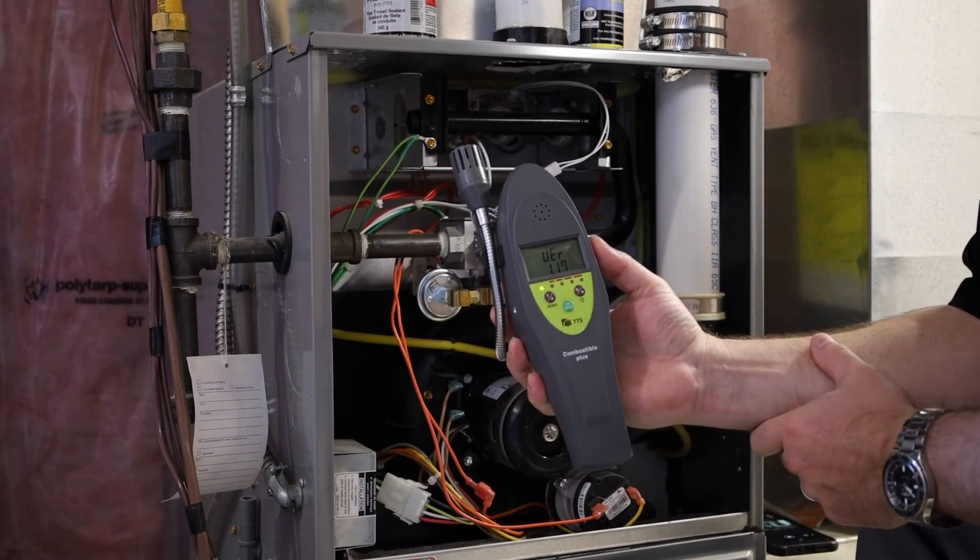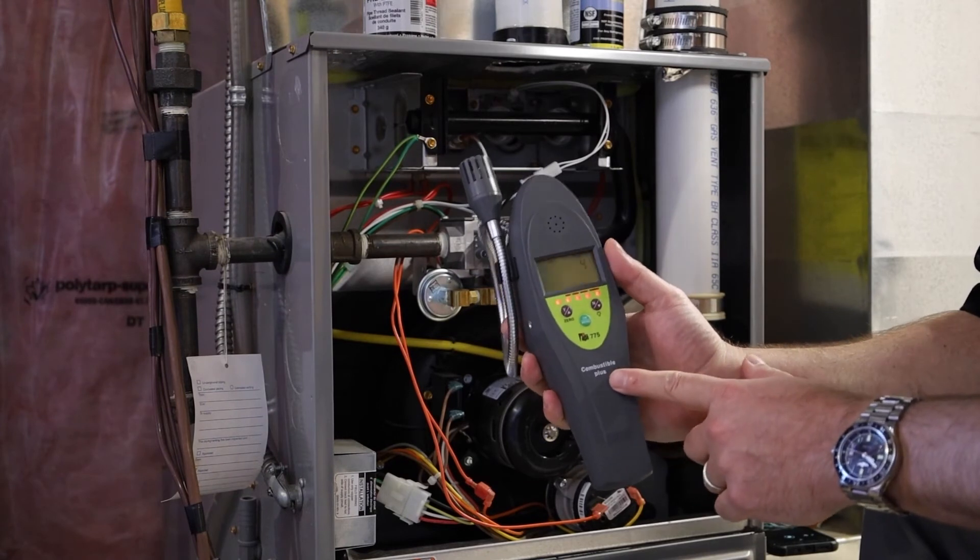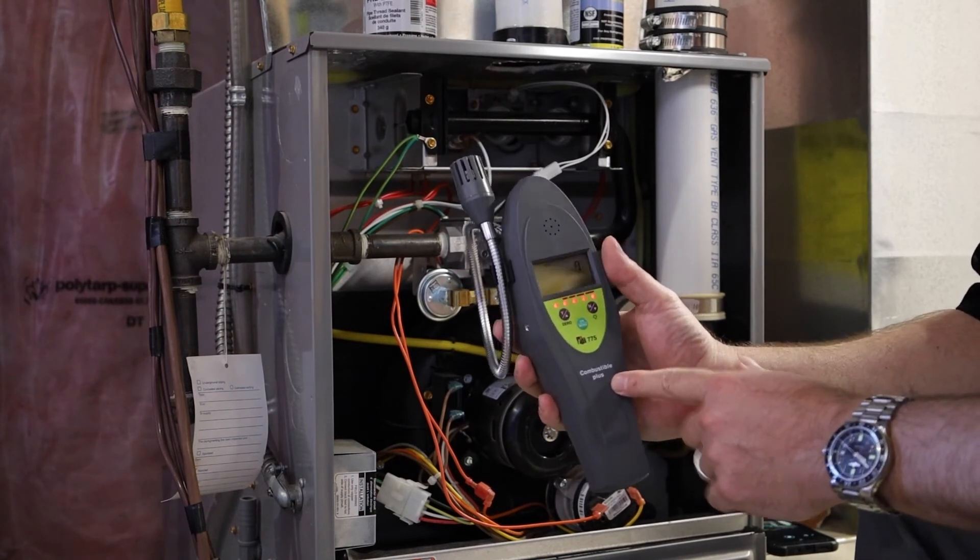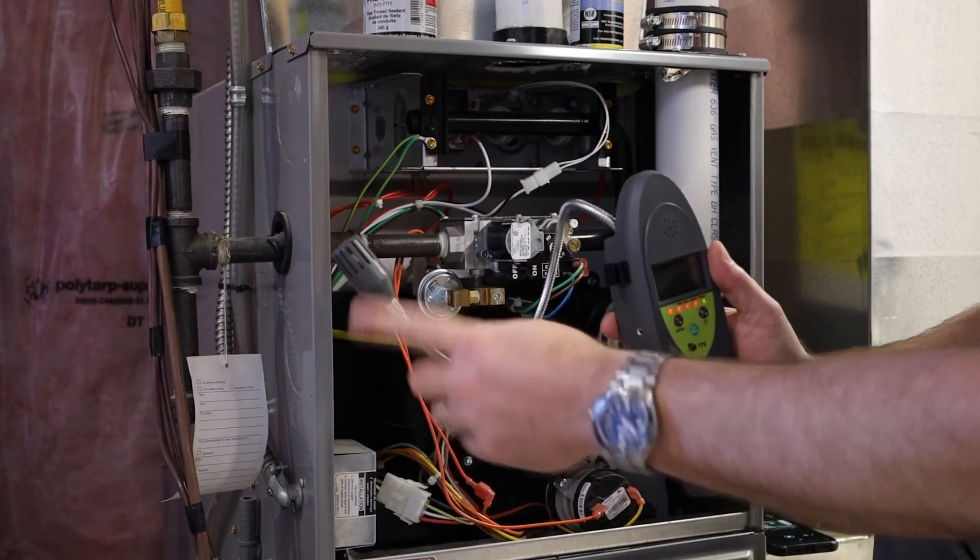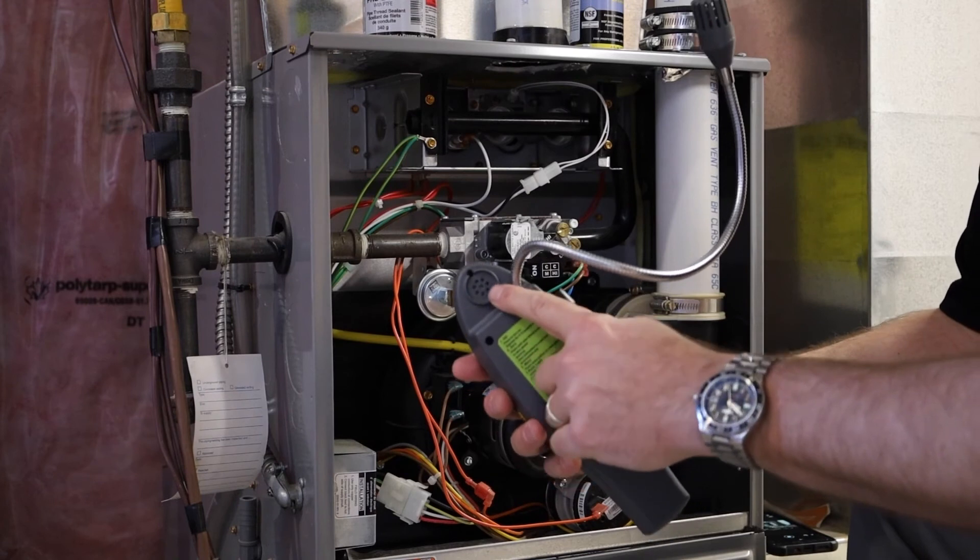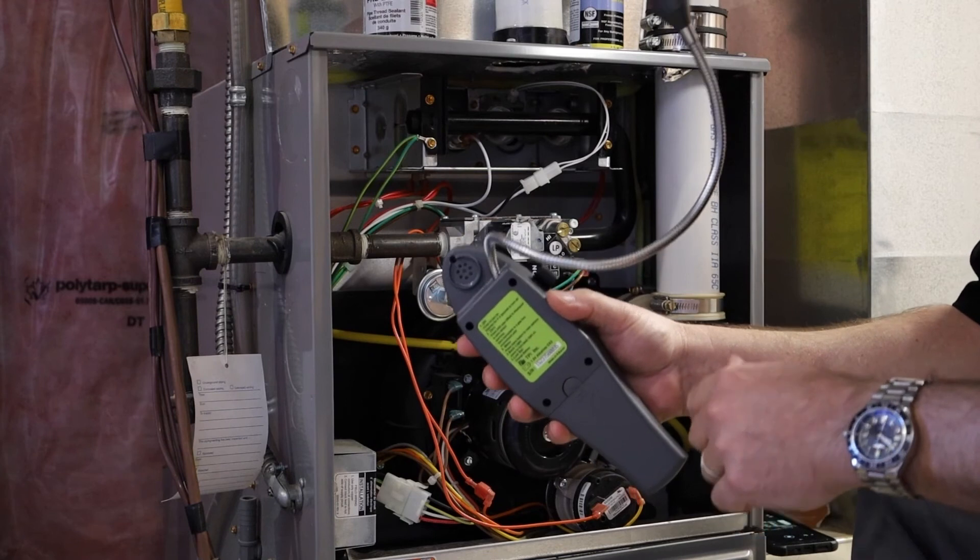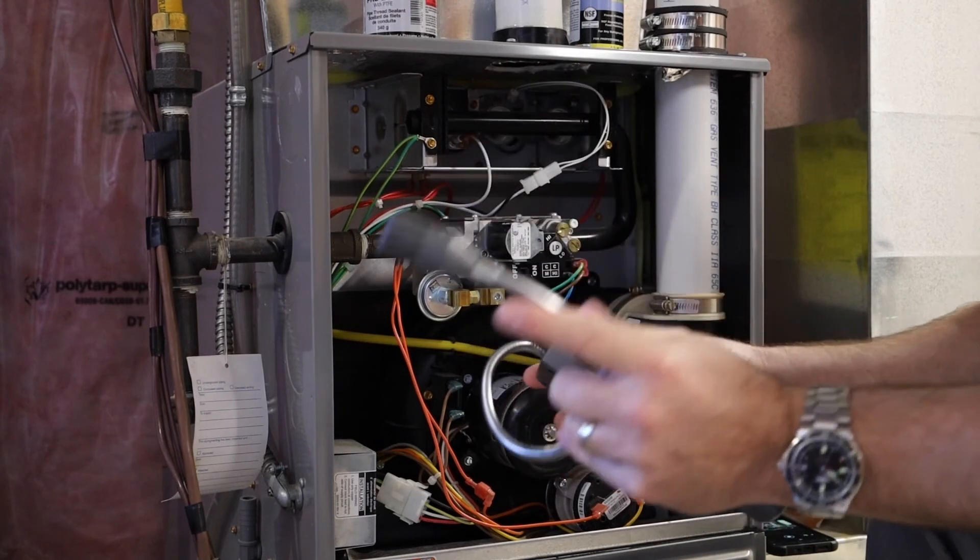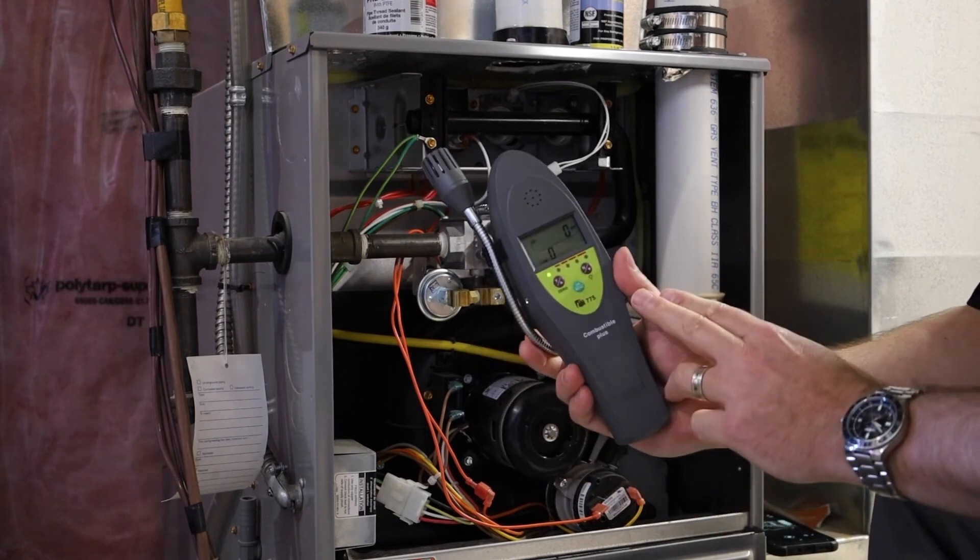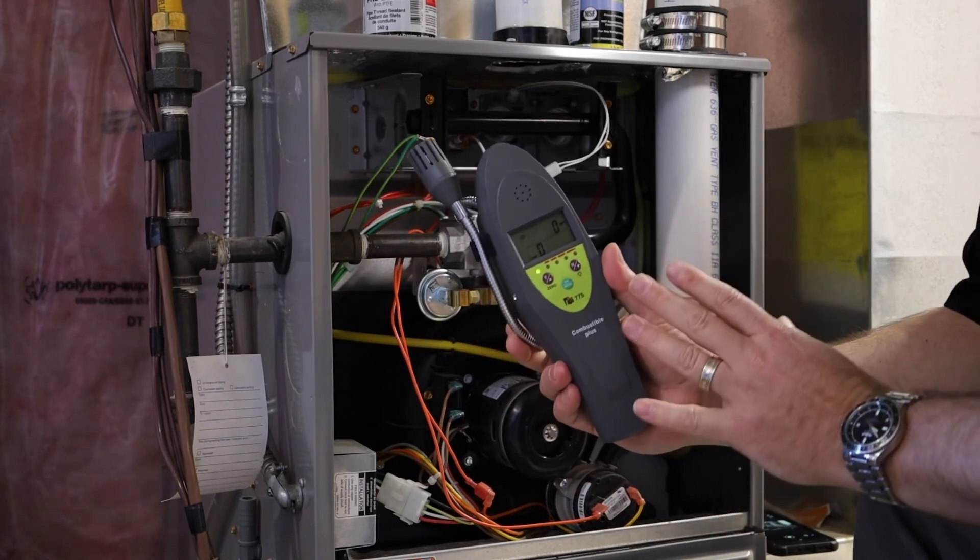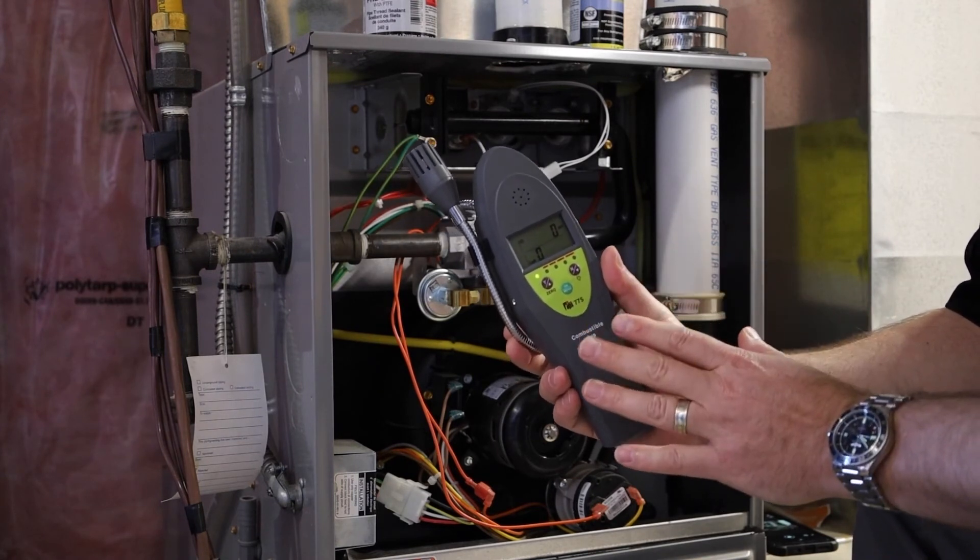Here's the 775 combustible plus. And the plus means it actually will measure CO, carbon monoxide. So it's got the flexible wand. And this is your combustible leak sensor. But if you turn the unit back over, right at the top here, that is where your CO sensor is. So it's going to be measuring carbon monoxide at the same time. So you're basically multitasking. Now with this unit, because it has a CO sensor in it, you have to turn it on outside in fresh air. You want to zero that CO sensor at zero parts per million.